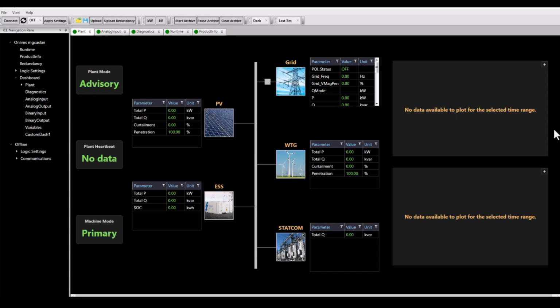At this stage, we have successfully closed the control loop. The EPPC is now actively managing plant operation, making real-time adjustments to optimize performance and ensure compliance with grid code requirements. Additionally, it communicates with both HMI and SCADA, which allows the operator to monitor and oversee system behavior in real time.